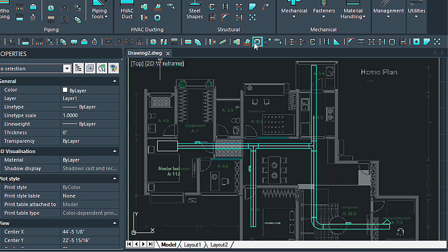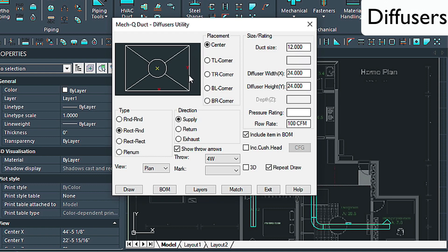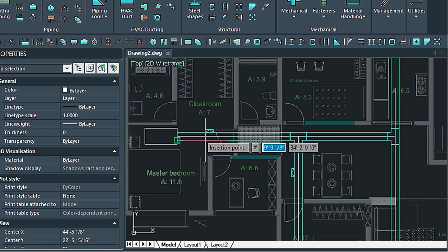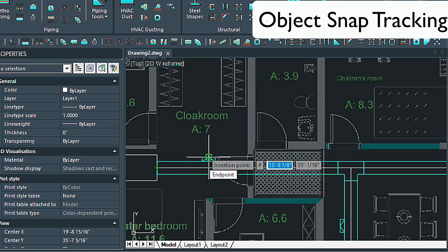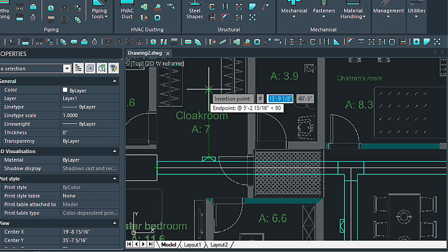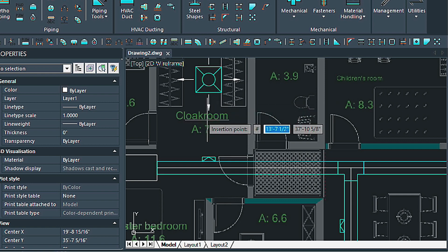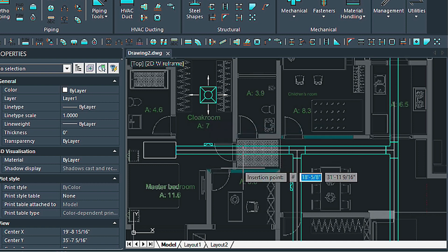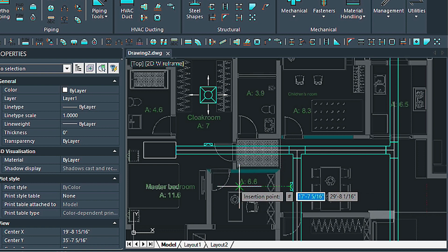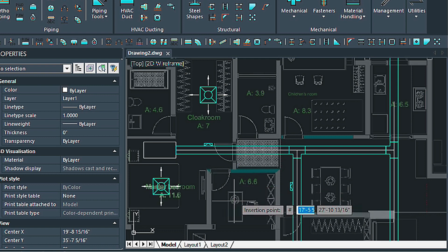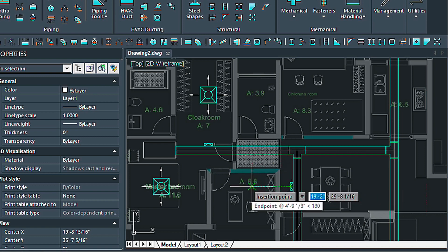Let's put in our diffusers now — we've got the diffuser utility here. Here we have a rectangular round diffuser with supply, the duct size is 12 — it probably should have been smaller — but we've got a 24 by 24 and everything looks good. Repeat draw is turned on. Let's use the snap tracking mechanism again: highlight over briefly, then come up with our construction line, go up about 6 feet, and that puts in our diffuser. We can do another one over here — let's say 16 feet over — and let's put another one in about 6 feet over.